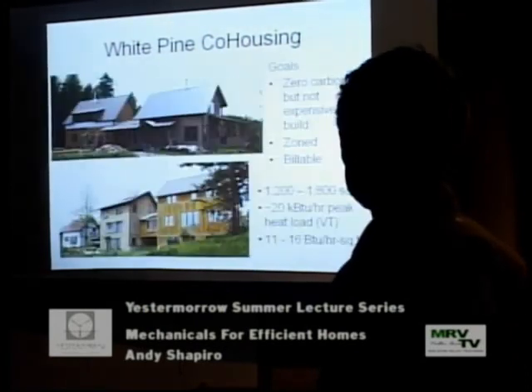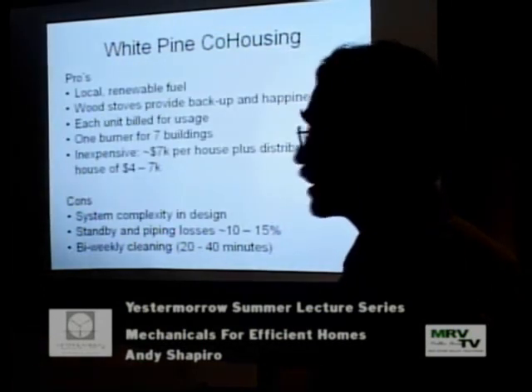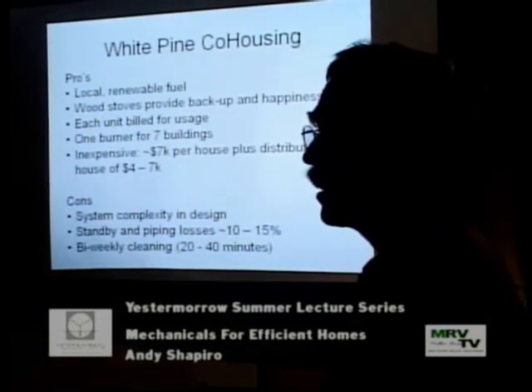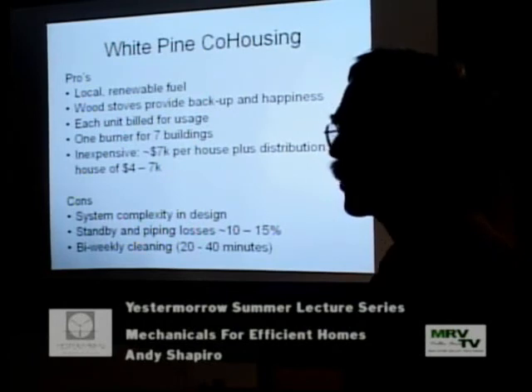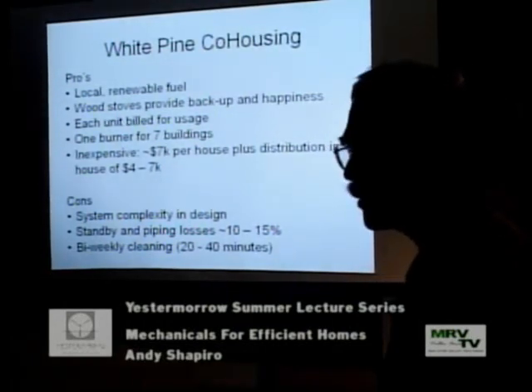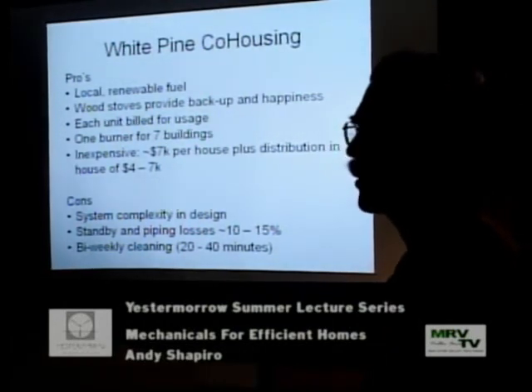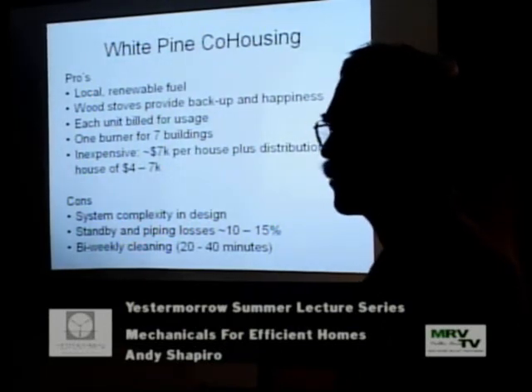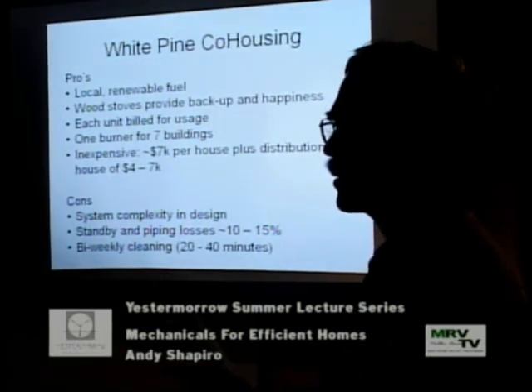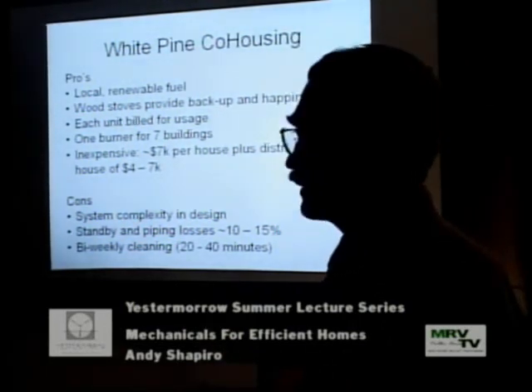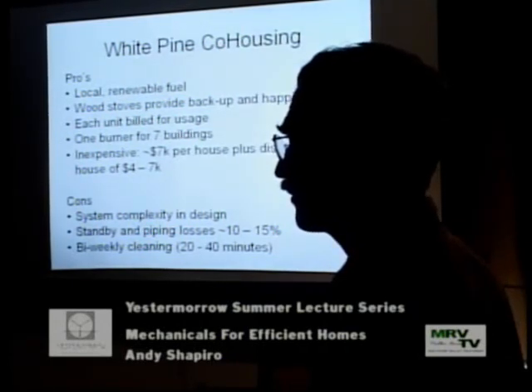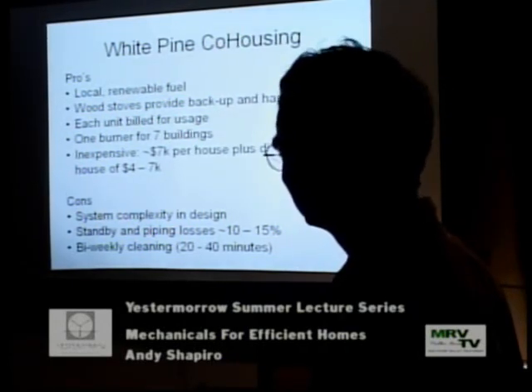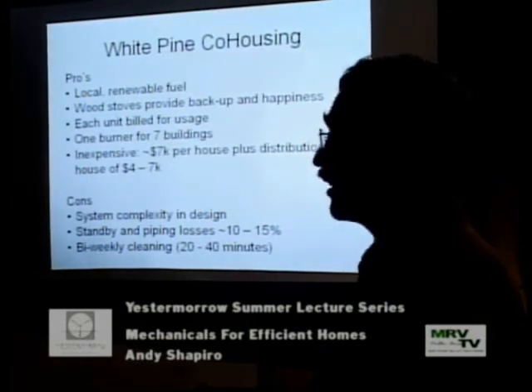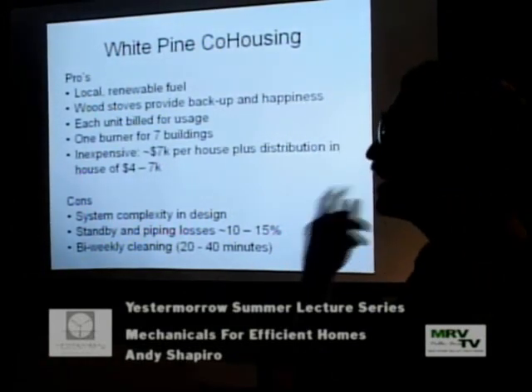So there is some significant standby losses. And it's a relatively high percentage for us because the loads are so low. Ordinarily, you think of this underground piping loss of maybe 5 to 10%. For us, they're like 10 or 20%, but it's because the load is low. But it's not enough to warm the soil to grow tropical fruits or something.